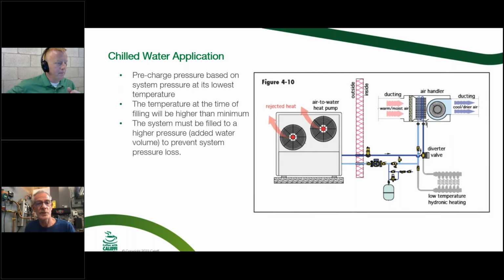Yeah, so here we go with the chilled water system. So same thing, the pressure is going to be based on the fill pressure at the lowest temperature. Now, if you're filling this thing with maybe 70-degree water coming into your house, or in Phoenix the water comes in at 80 degrees, you've got to know that that water is going to contract as you cool it down to 55 degrees or whatever you're going to chill that water to. So we've got to be able to accommodate that temperature swing as we chill the water also.